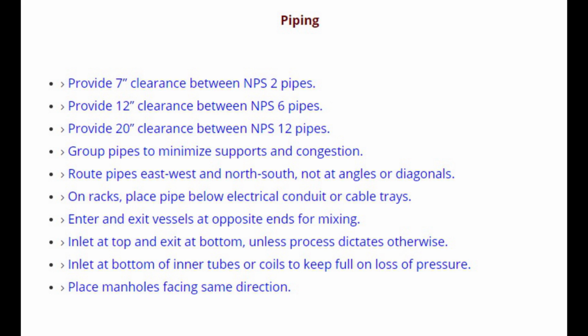Number 8. Inlet at top and exit at bottom, unless process dictates otherwise. Number 9. Inlet at bottom of inner tubes or coils to keep full on loss of pressure. Number 10. Place manholes facing same direction.